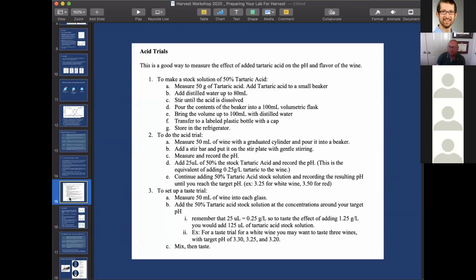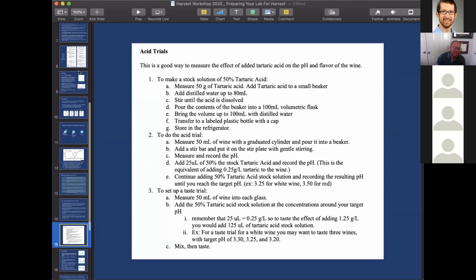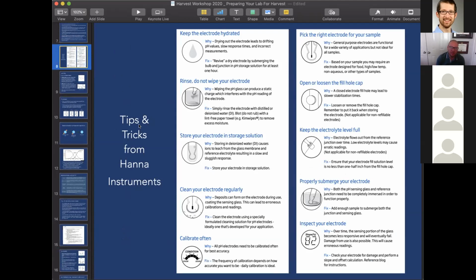David, can you just, because I see it a lot when I'm traveling around, or last year I did: what happens to your pH probe when you don't store it in anything? You just leave it on the counter dry? Well, it definitely will dry out, and that moisture is needed in order for it to work. If you're not keeping it hydrated, you'll see drifting, slow response times, and incorrect measurements. That is the problem. You're getting that drying on a semi-permeable glass, and so you can have some clouding and problems. And then what Hanna recommends here is that you can start to revive it after a certain period, but in my experience, that does not work very well. Yeah, no, in my experience also, no.